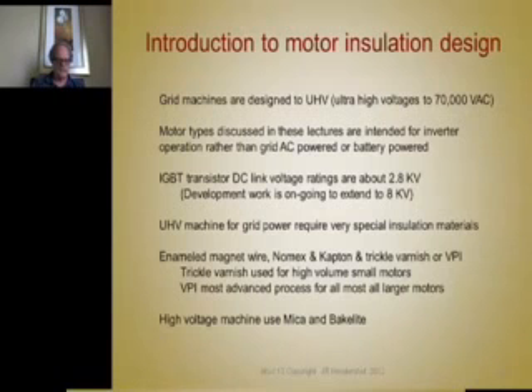A little preheating, and then trickle the varnish out of nozzles onto the end turns while you rotate the stator, and then the heat and capillary action suck the varnish in between the conductors and down the slots, and there's very little mess and cleanup with this. And for larger motors, they're all VPI insulated. High voltage machines use these, and ultra high voltage machines use mica and bakelite and various thick slabs of insulation materials.